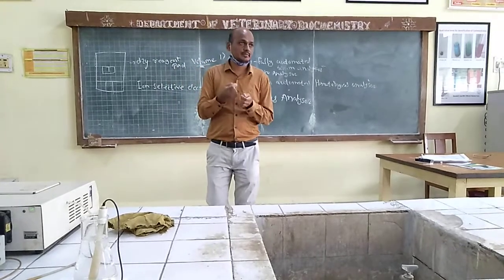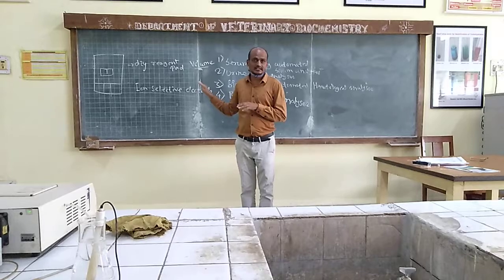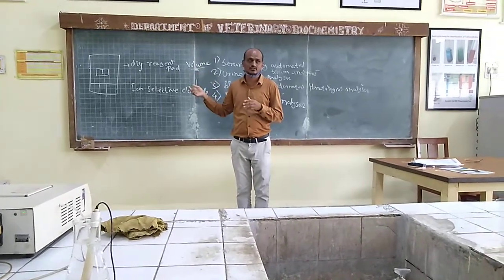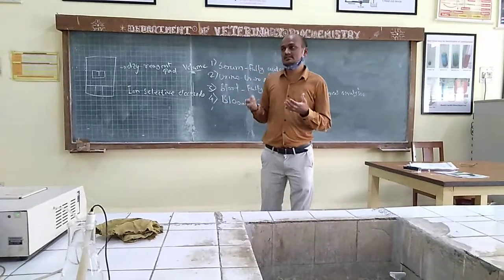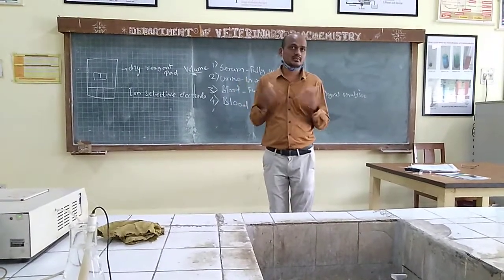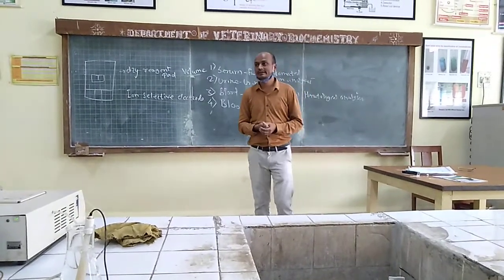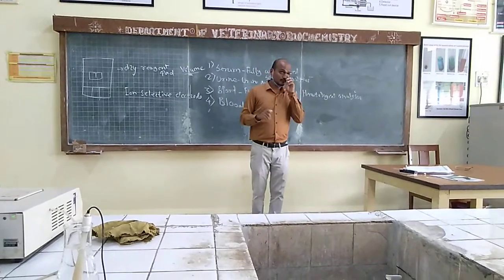So we have ion selective electrode technology inserted in this one. So it will be reacting. Hydrogen exchange will happen at the electrode position, and based on the potentiometric method, this ion flow will be measured, and based on that we say, okay, the pH is 7, or pH is 4, or it is 8. So that is the principle of this equipment.